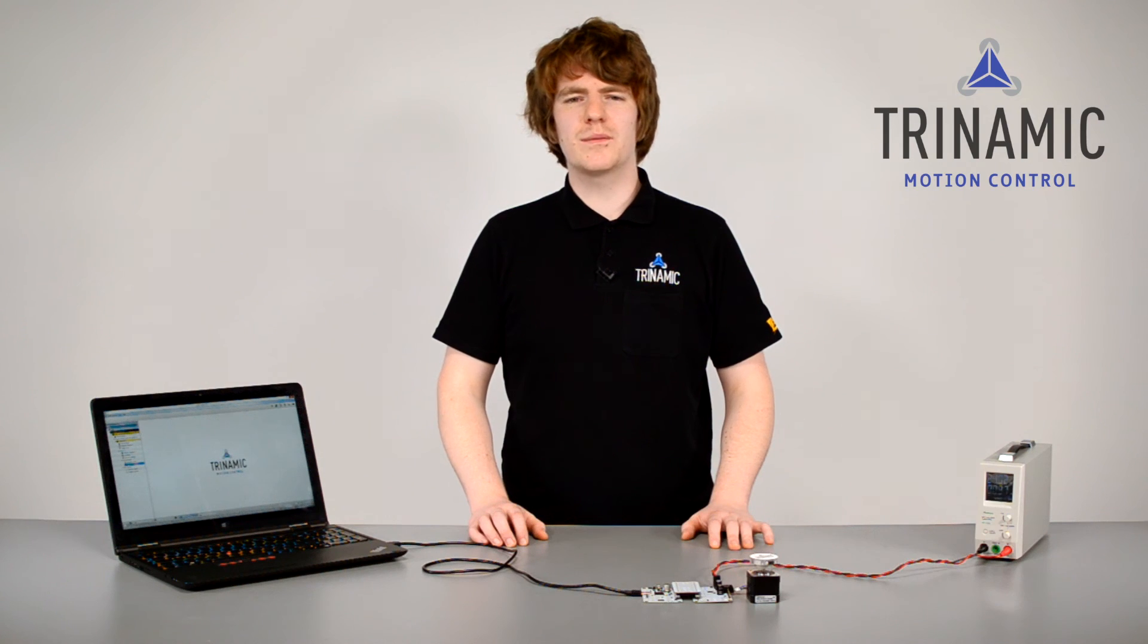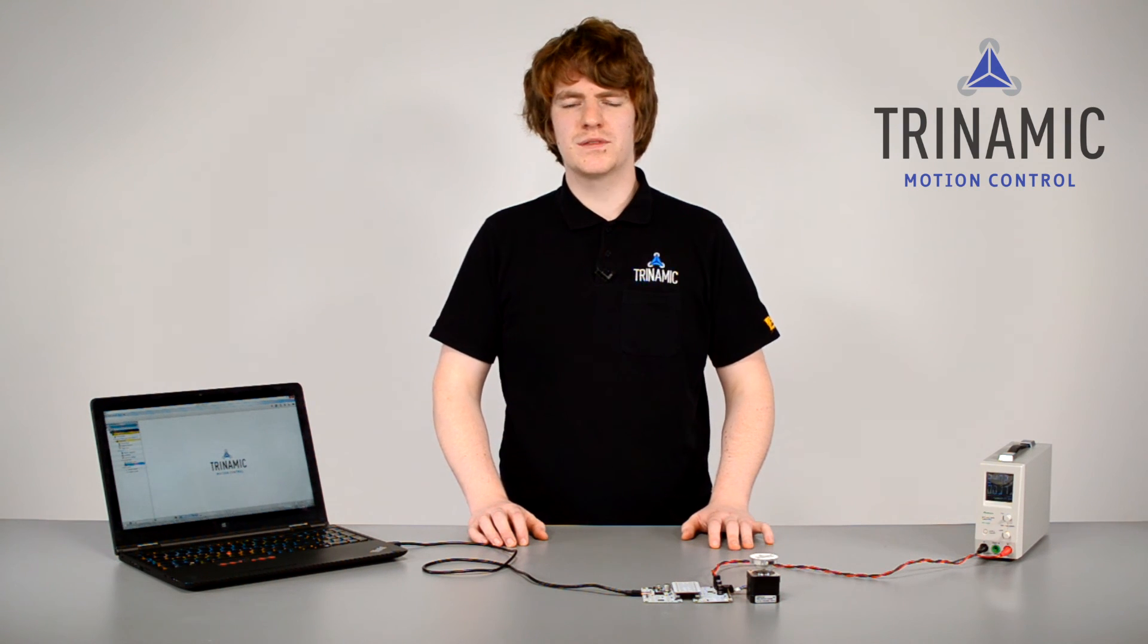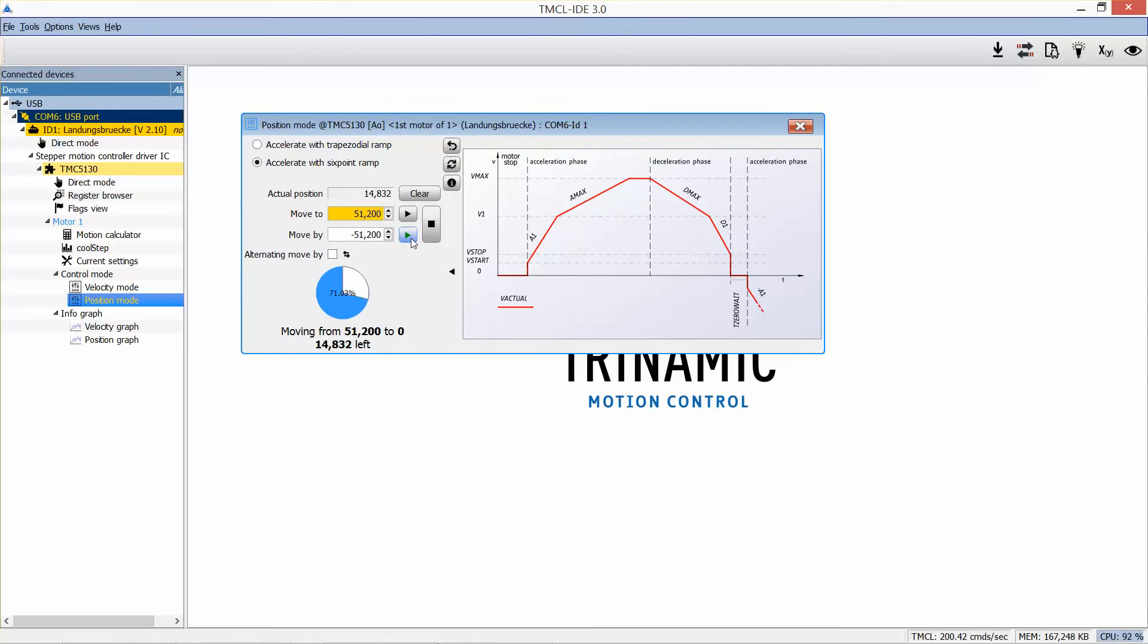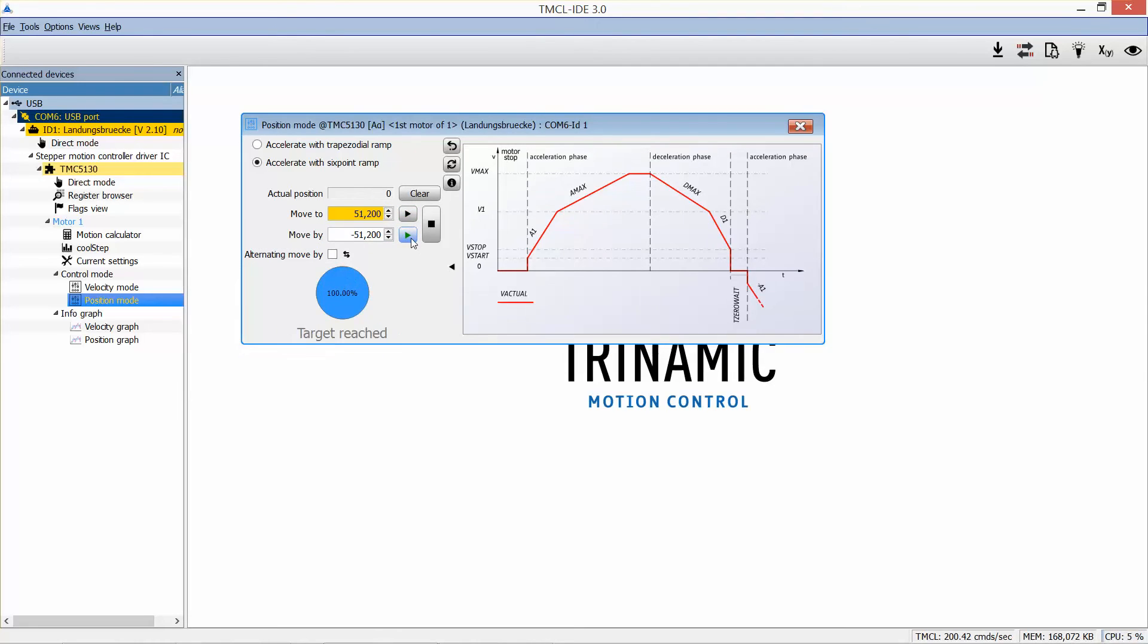With these parameters, you can optimize the settings for your application. The hardware ramp generator produces smooth ramps and sticks to acceleration and deceleration values, even if you change them on the fly. Once the ramp is set up, we can enter a target position and press play again.